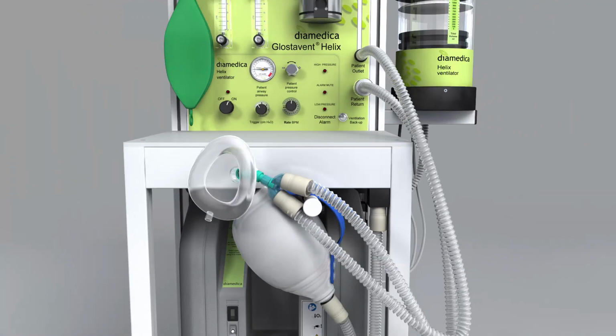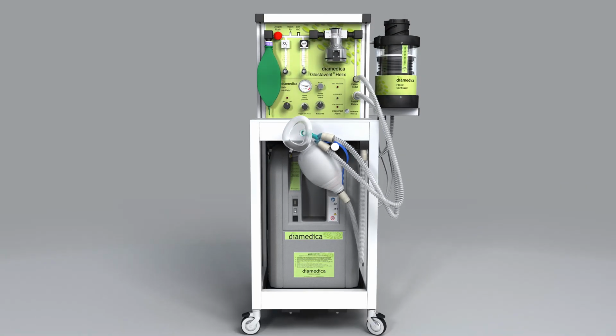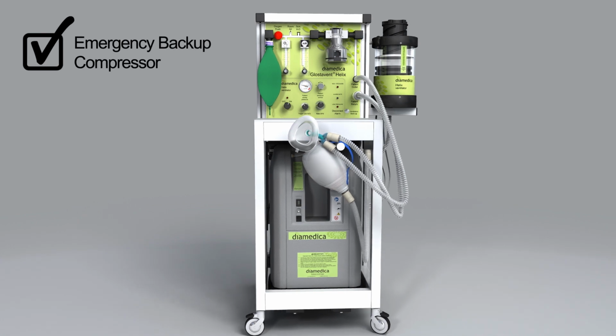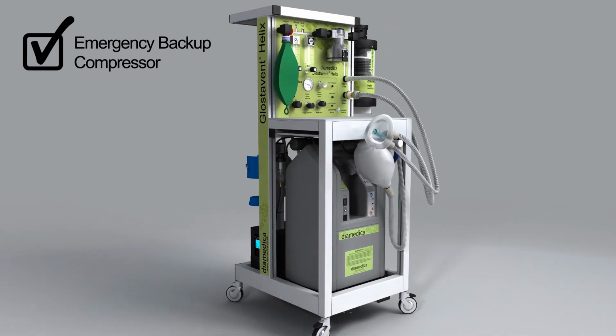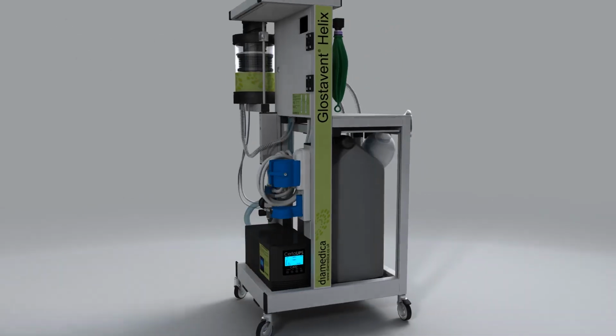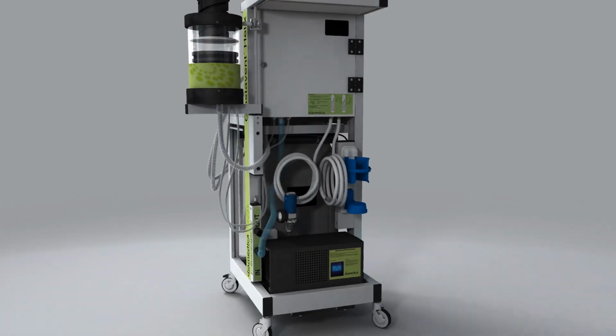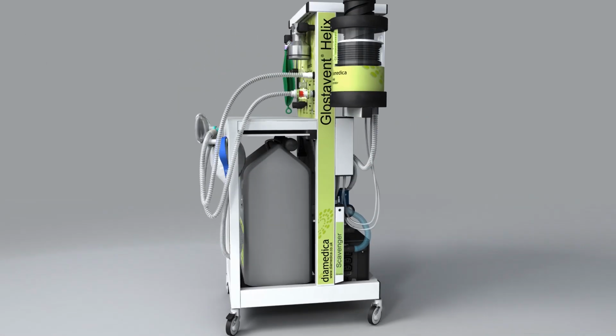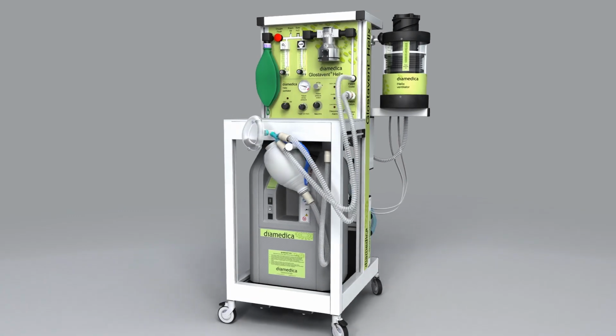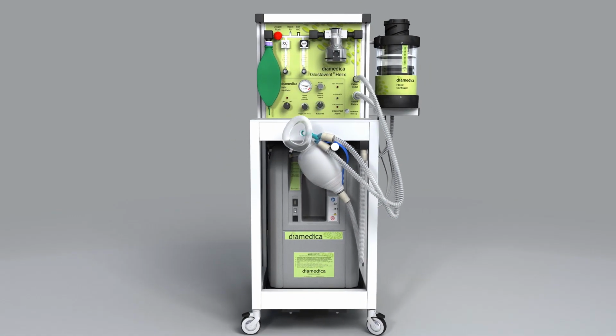If the UPS batteries have discharged and there is a power failure, then there is an emergency backup compressor which will run the ventilator on room air for approximately 12 hours. A minimal amount of gas is used to drive the ventilator, making it economical to use when oxygen is not readily available. The gas used to drive the ventilator is recycled back into the circuit to reduce the amount of oxygen needed to run the machine.